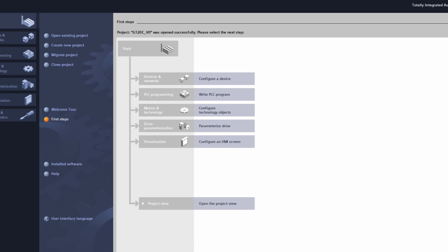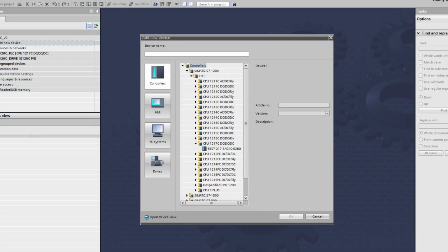Today I'll show you the fastest way to connect a SINAMICS G120C PROFINET drive to an S7-1200 in TIA Portal using Telegram 1, mapping the PZD words, and controlling it with a simple FB.